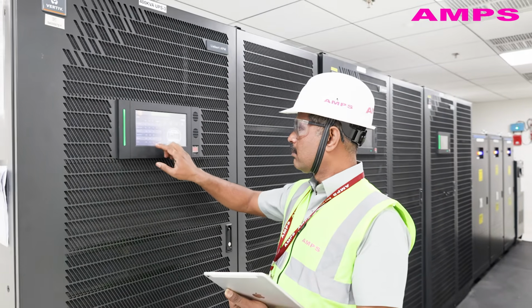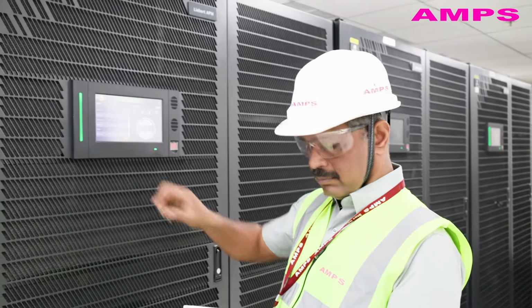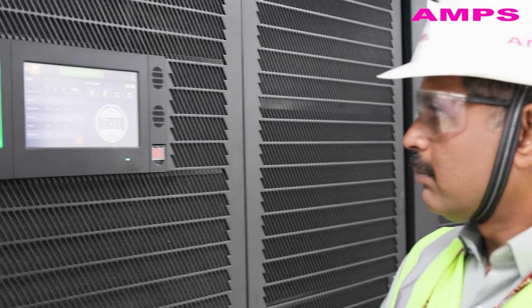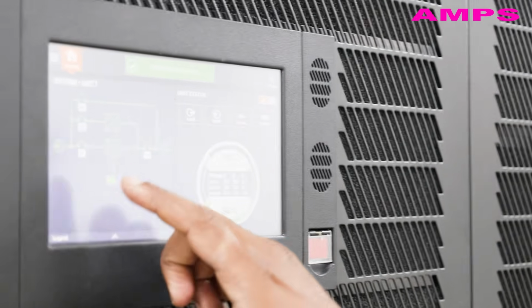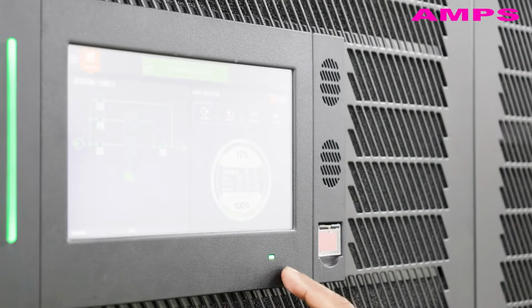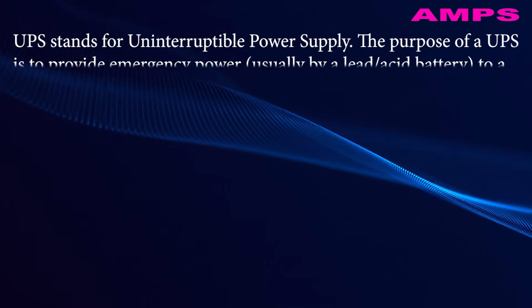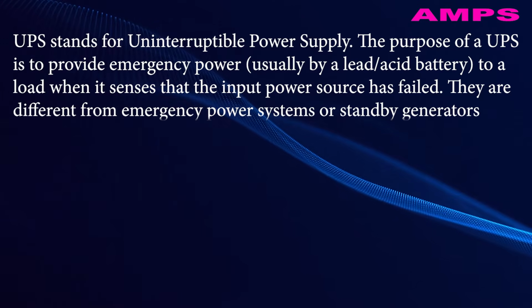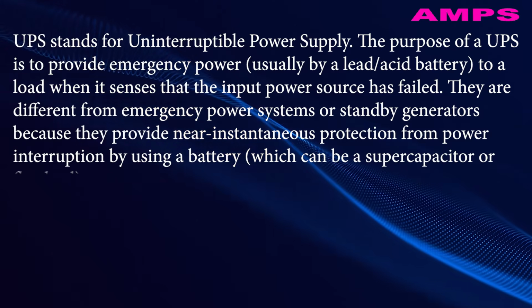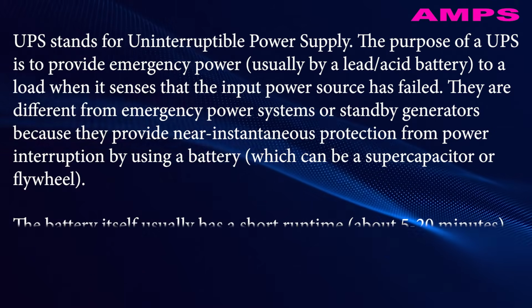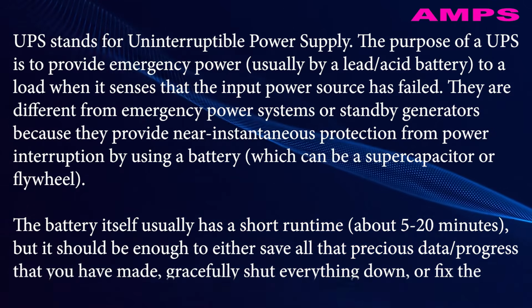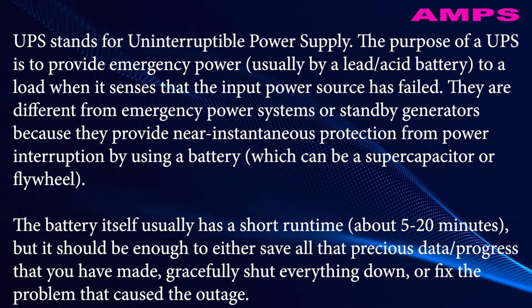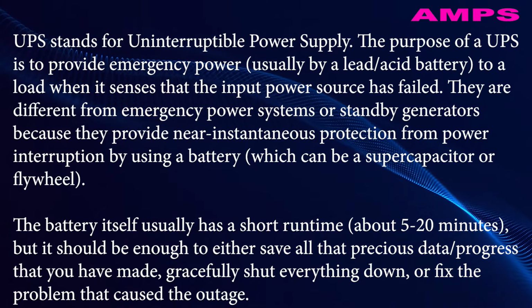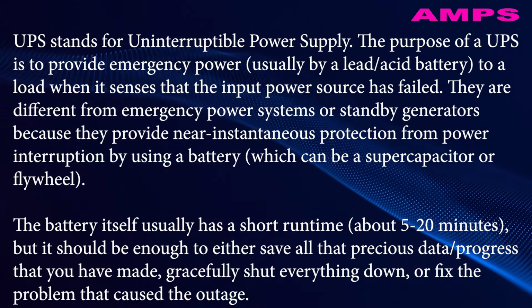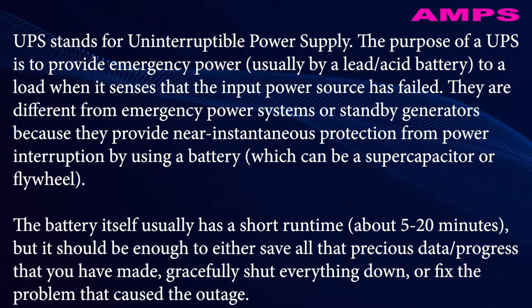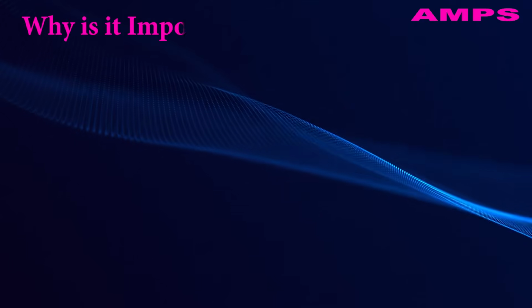They are different from emergency power systems or standby generators because they provide near instantaneous protection from power interruption by using a battery, which can be a supercapacitor or flywheel. The battery itself usually has a short runtime, about 5 to 20 minutes, but it should be enough to either save all that precious data or progress that you have made, gracefully shut everything down, or fix the problem that caused the outage. Why is it important?